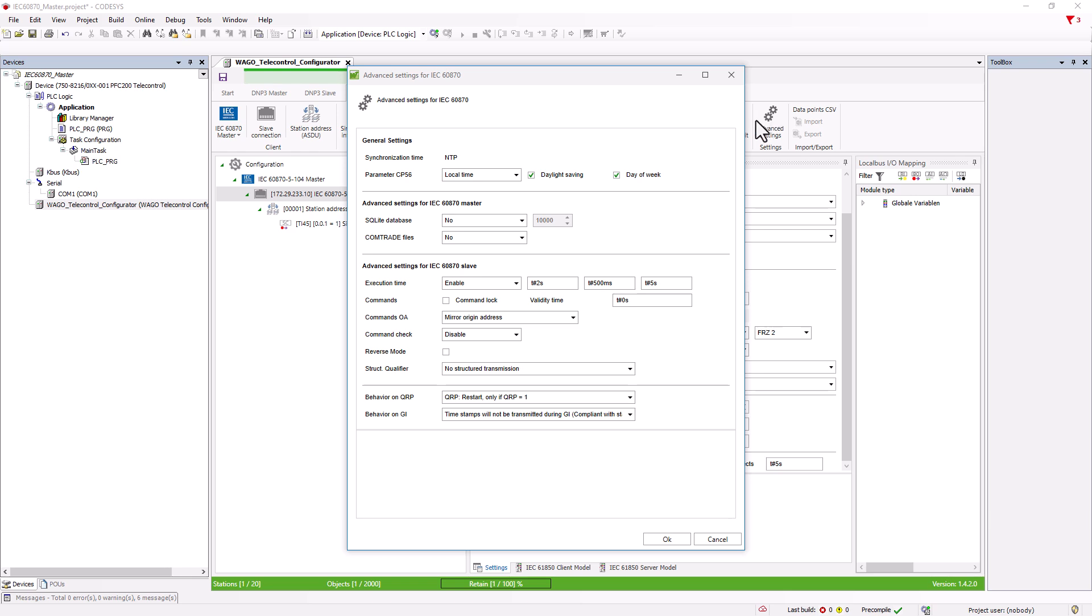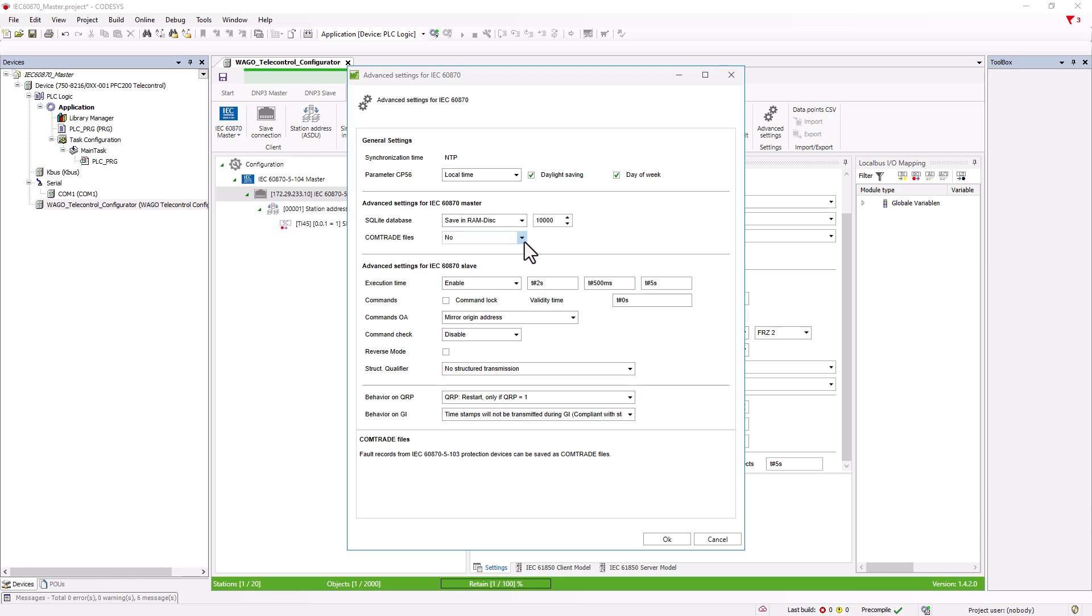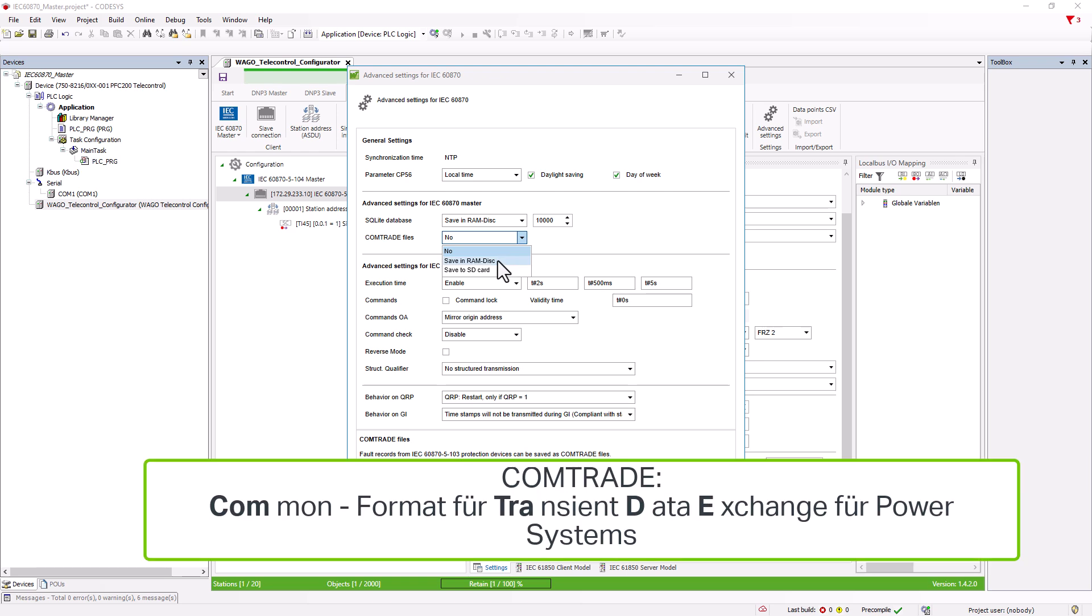In the advanced settings, we have the option for the master to store the received data in a SQLite database by assigning the storage locations here, either in the controller's RAM or on an SD card. The maximum number of records to be stored is specified in the field behind this. If this limit is exceeded by 10%, the oldest records are deleted. The fault records of 103 protection devices can also be saved as a Comtrade file.